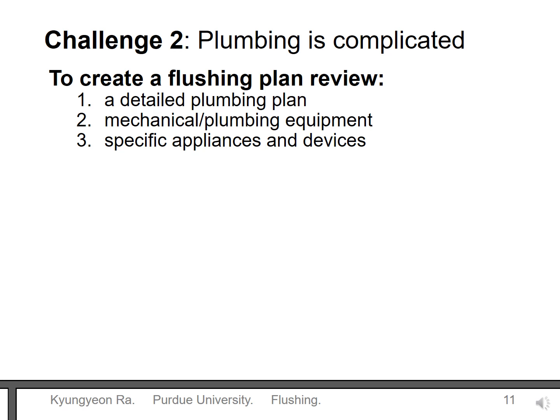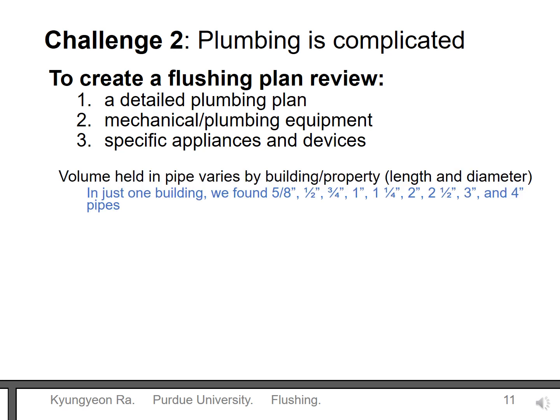Another challenge is that plumbing is not so simple. Even with just the simple animation you just saw, you learned that we need to really understand how the building water system is set up. A detailed plumbing diagram can be extremely helpful to create a flushing plan. You also need to know which mechanical and plumbing equipment exist in the building and where. These include devices such as softeners, heater tanks, and specific devices like ice machines and point-of-use devices like faucet or under-sink filters. In one building we found there were numerous pipes of different diameters even along the same water line. To flush completely, it is important to know how much volume you need to flush and how long flushing will take.